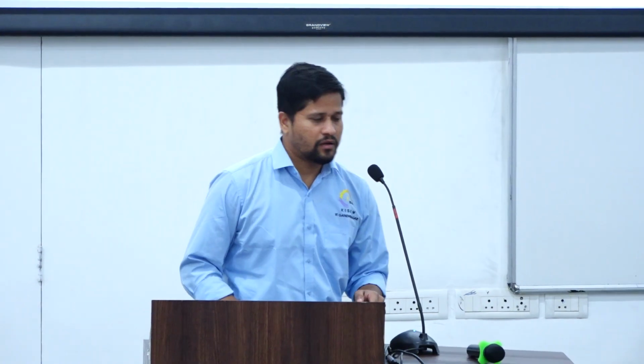Yes. Hi everyone. For power quality measurement, we have a dedicated instrument, the power quality analyzer. Can you just open? With the help of this power quality analyzer, in any industry we can do mainline monitoring of power. In this instrument we can measure active power, apparent power, reactive power, percentage of harmonics, power factor, etc.